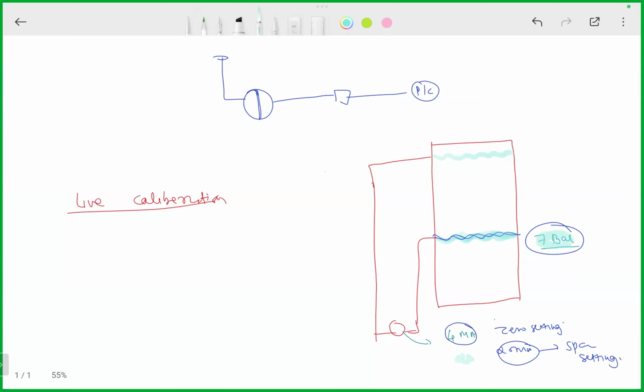Slight variation in the pressure is acceptable. That is going to mimic the exact level achieved at low level and high level. Those will be verified by the gauge glasses, right, sir? Yeah, gauge glasses. Absolutely correct. And sir, we have to maintain the same pressure on the low level and the high level. Then only calibration is right.